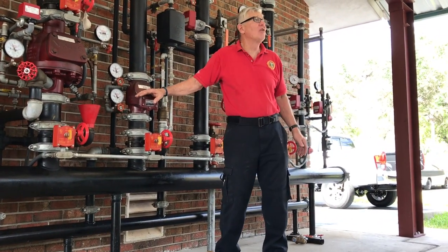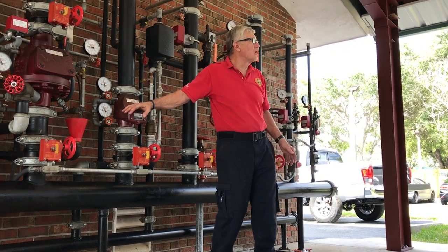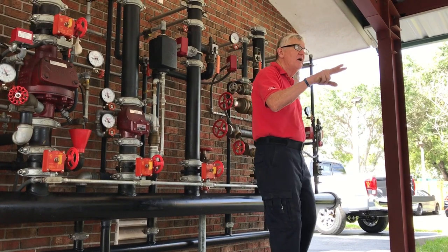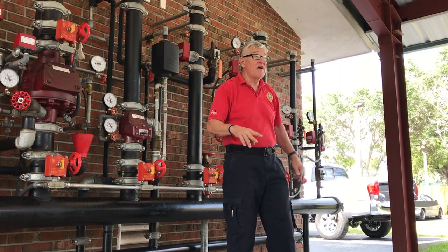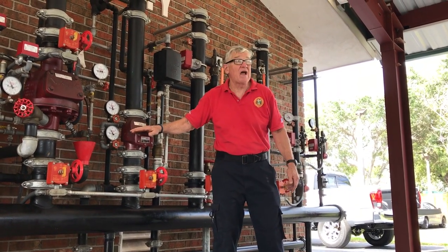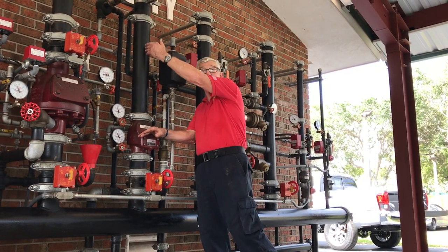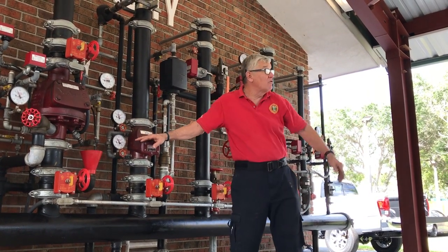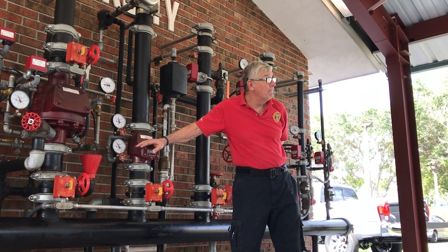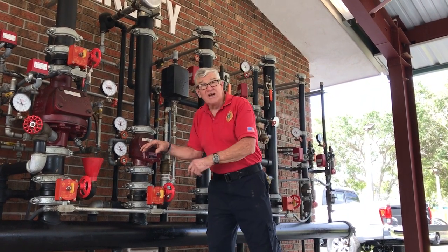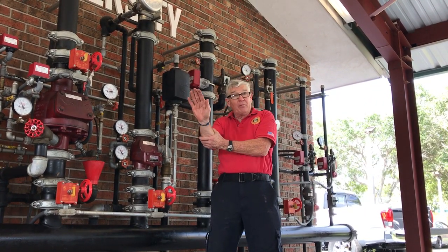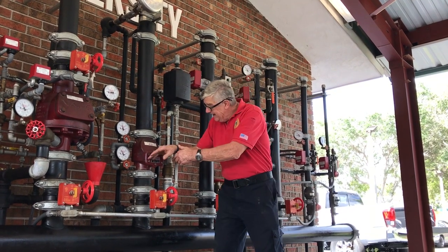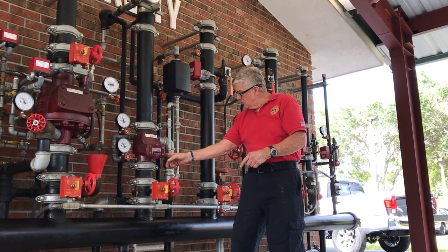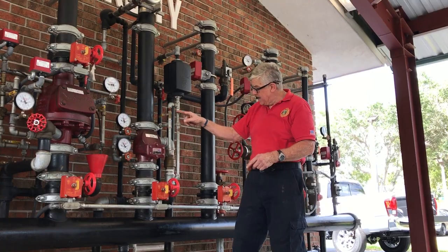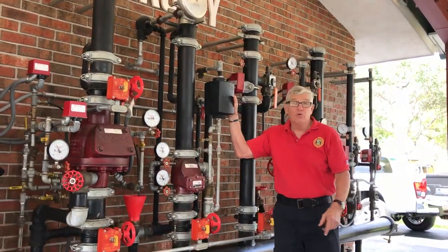You have what's called an alarm check valve, which serves two purposes. One, before they had backflow prevention devices, this would prevent backflow. This would prevent the column of water from going back into the potable water supply.